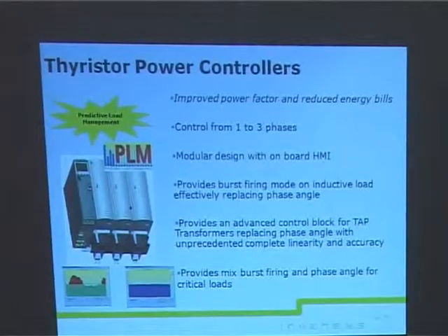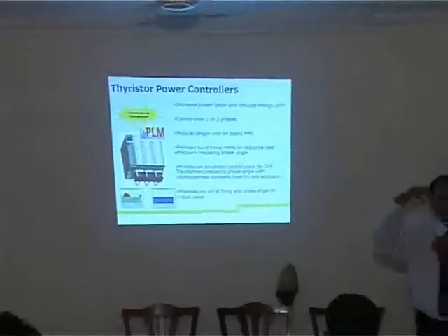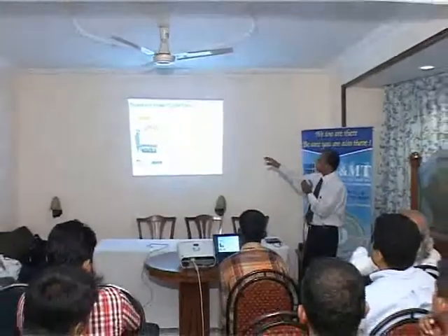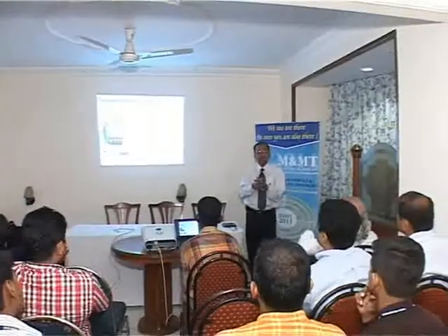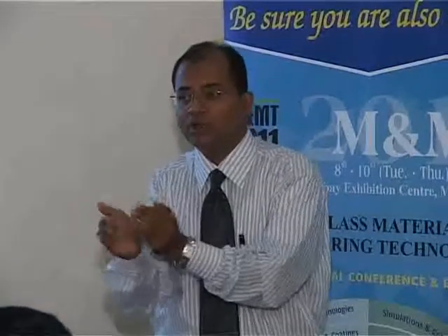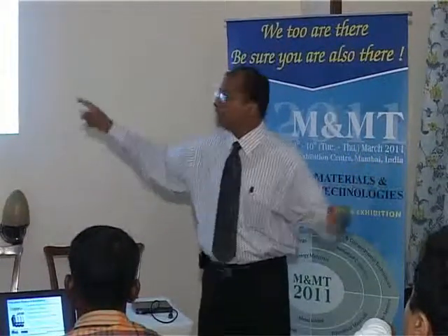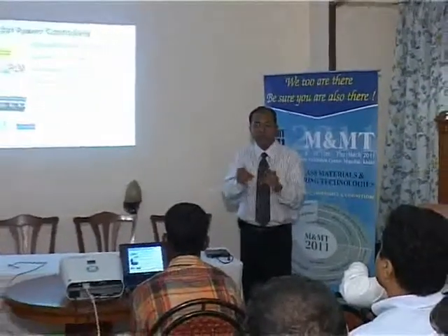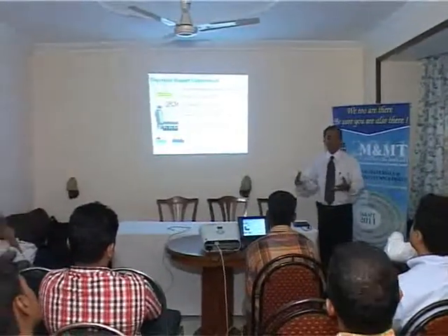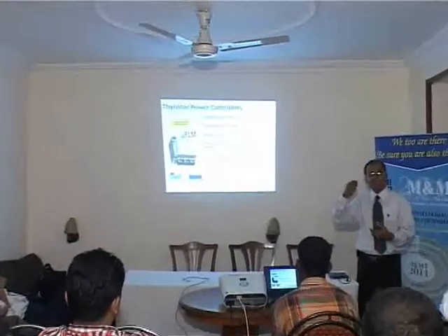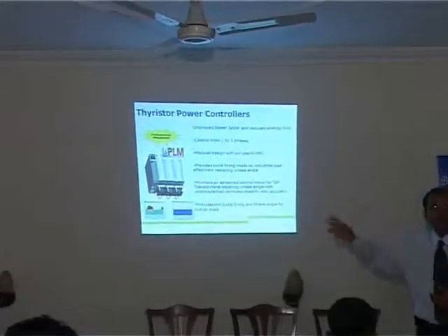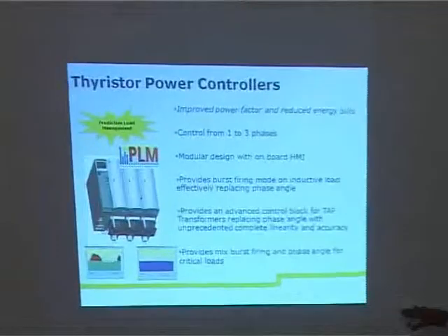The reason I am walking you through this is to give you an idea that all this is available. It's only about getting aware and making use of it. Now by doing this, what happens? Modular design gives you PLM, predictive load management. Supposing you have a number of furnaces and a large load, and you have uneven, uncontrolled on-off happening of the furnaces, you will give a lot of disturbance to the electrical supply. This may not be applicable for a user of 2-3 furnaces, but if you have a larger furnace-centric install base, it could be a massive cost of electricity. That can be controlled if the usage of power on-off is regularized. If you know all this today, and come across a situation tomorrow, you will know that something like this is available. Then you can search for it and make use of it.